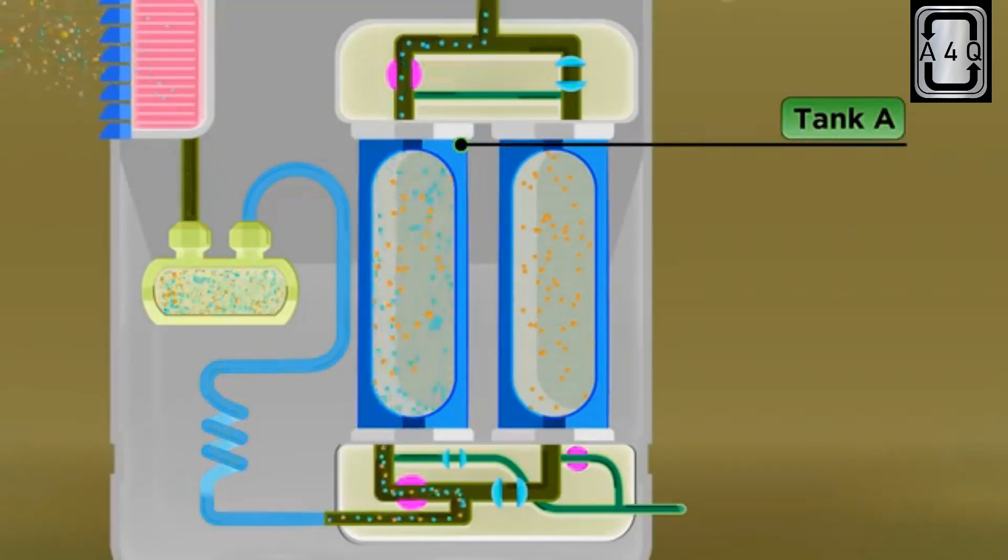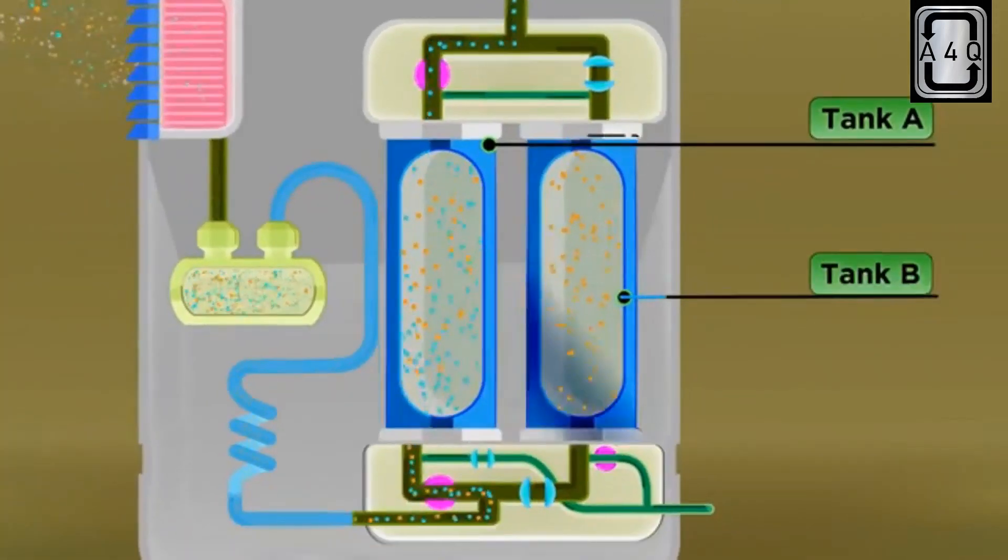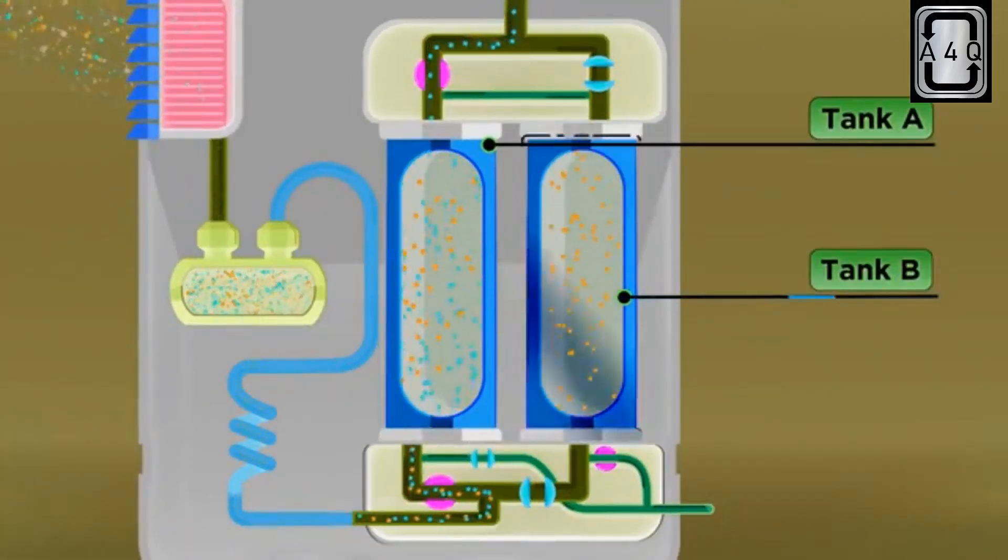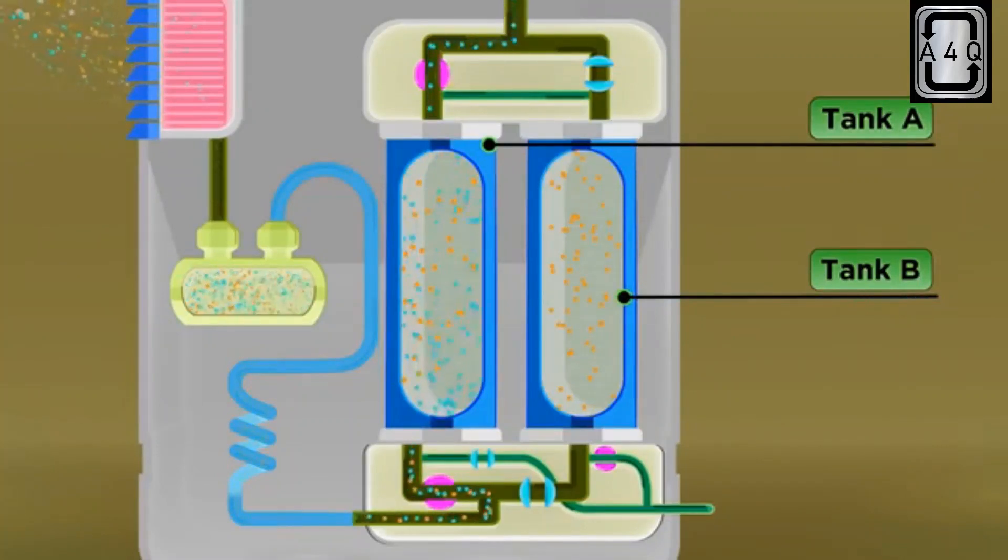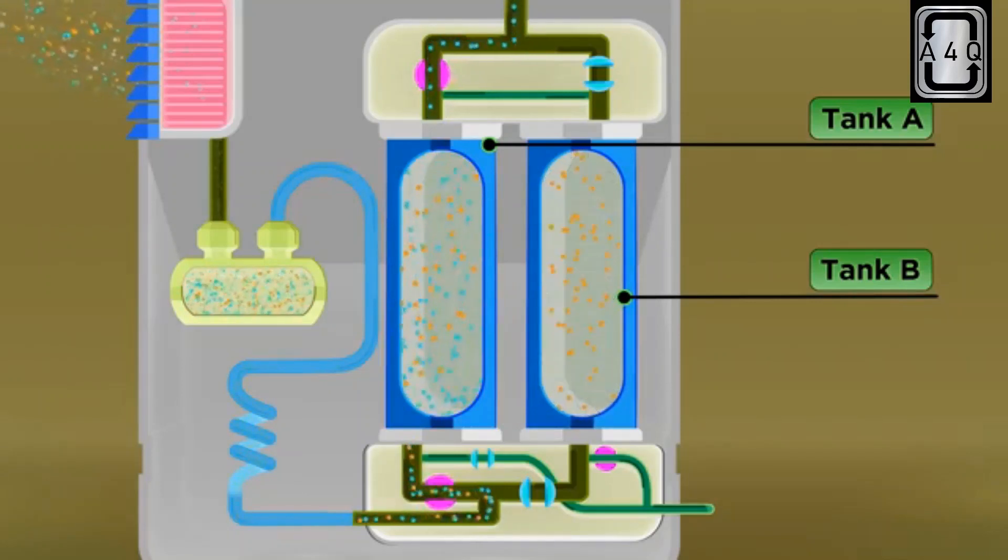Meantime, in tank B, there is no high pressure air passing through, which means that when the pressure reduces, the nitrogen molecules that were stuck to the zeolite filter now start floating around, and part of this pure oxygen from tank A passes through tank B in a reverse flow to remove all these floating nitrogen molecules.